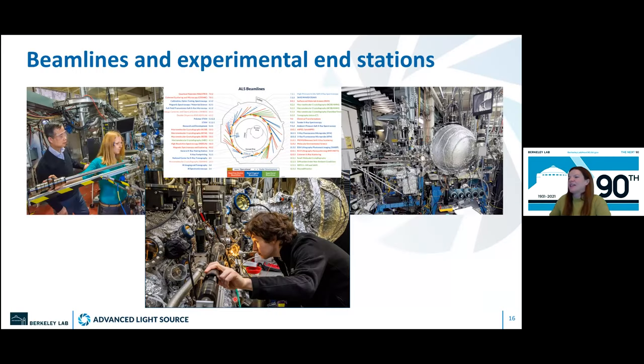So these are the beam lines with the experimental end stations. What that means is the place where you put your sample. And they have to be under high vacuum, a vacuum that's kind of similar to the surface of the moon in the beam line, because these X-rays, the light that we produce, are easily absorbed in air. So we have to take away all the air out of the instrument in order to get those X-rays to your sample, to study what's going on inside.